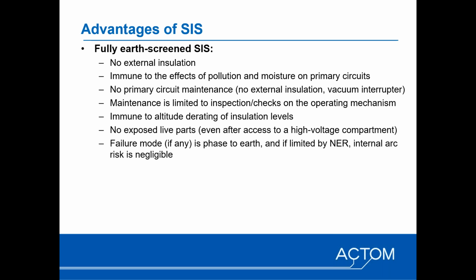So then, in terms of fully screened, earth-screened SIS, the benefit is that there is no exposed external insulation, so it is effectively immune to the effects of pollution and moisture on the primary circuits. No maintenance is required on the primary circuit. We wouldn't claim that it's maintenance free, because as with other fixed pattern or GIS solutions, inspections and checks are still required on the operating mechanism. The big benefit, along with pressurized GIS solutions, is that it's immune to altitude derating of the insulation levels.